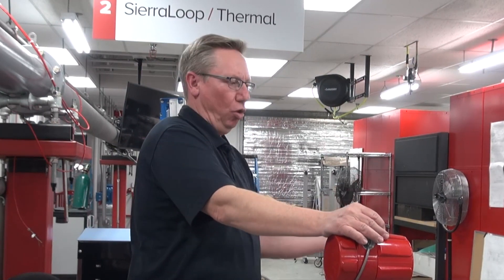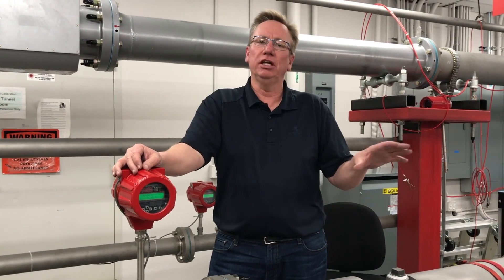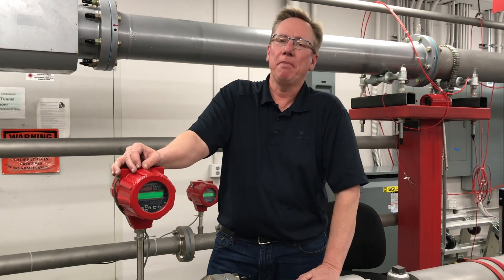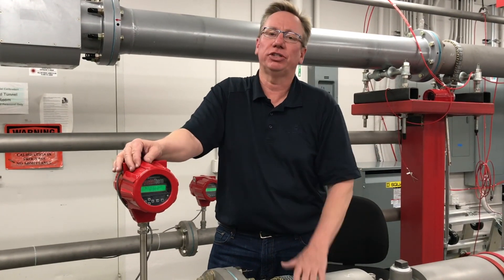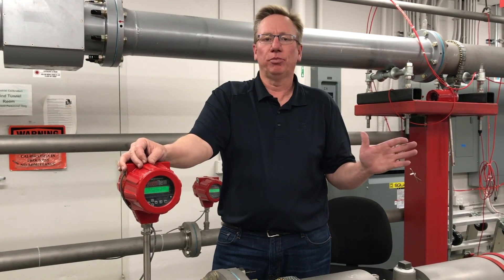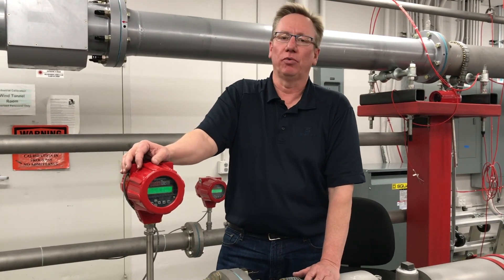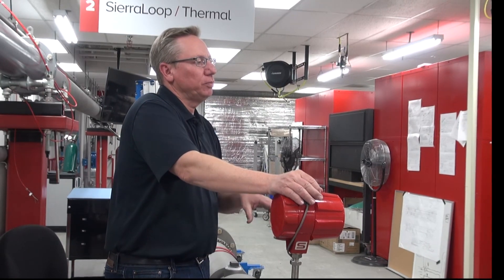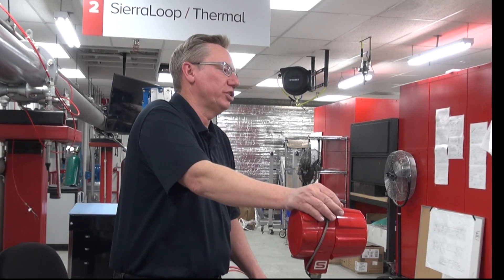You need to be able to capture low flows and very high flows, because all of that methane is combusted into energy that then turns into steam energy. So you want to measure that methane energy as accurately as you can and across the widest range possible. That's where Sierra thermal mass flow meters come in to help with that challenge. Any one of our thermal mass flow meters can measure all the way to zero flow and way up to very high flow rates, ensuring you capture the most accurate mass flow measurement of your methane for a correct boiler efficiency calculation.